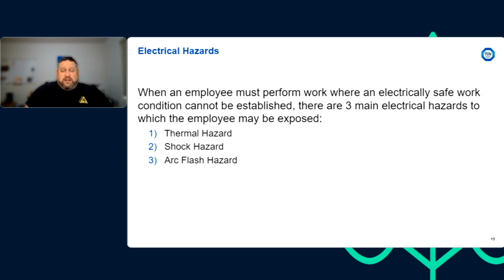Arc flash hazard for DC becomes a concern anytime we exceed 150 volts. So if any part of a high voltage battery system exceeds 150 volts, we have to evaluate that arc flash hazard, account for the protective devices, and calculate how much heat energy could be released in the case of a short or arc flash. Unlike shorting the battery with a screwdriver, that heat expands outward in a plasma cloud, touching our face and chest and possibly enveloping us, causing immediate third-degree burns.